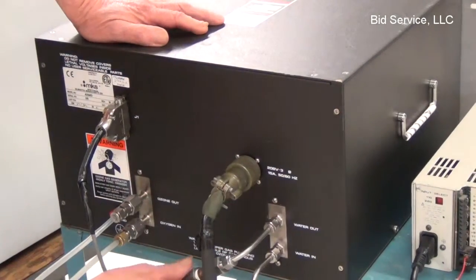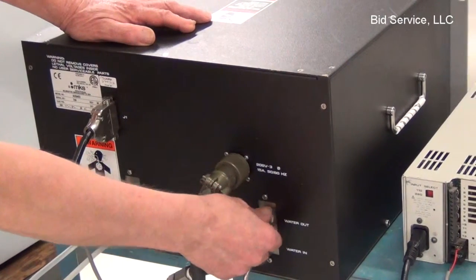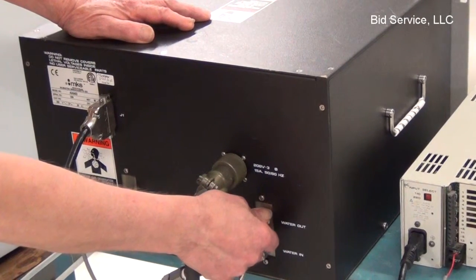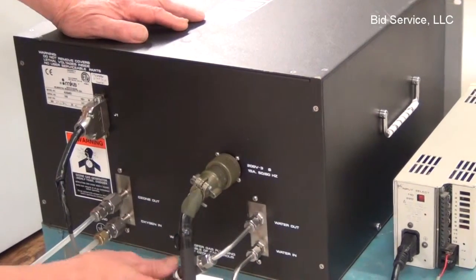It is a water-cooled instrument, requiring cooling water at 20 degrees C with pressure between 5 to 20 psi.